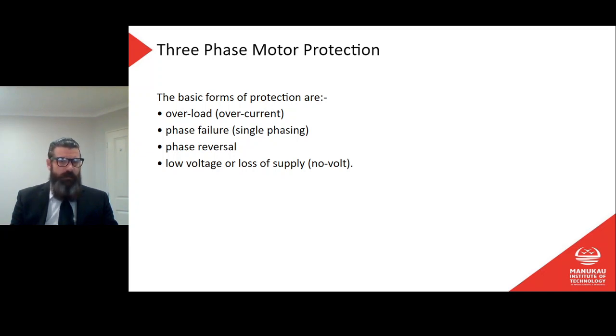So this is where if the power gets turned off for whatever reason, then we need some sort of no volt supply, which means that when the power comes back on, it doesn't automatically restart. So if you think of, say, the lights in your house, right? If the power goes off and you leave the light switch on, then when the power comes back on, the lights will go on. So they automatically come back on because the switch is left on. We don't want that to happen with most motors.